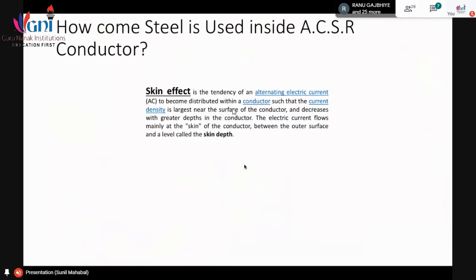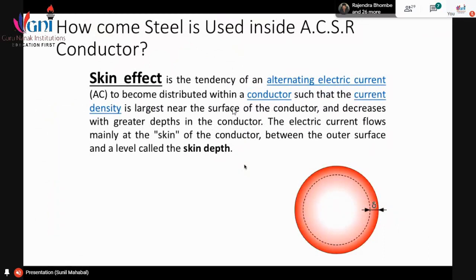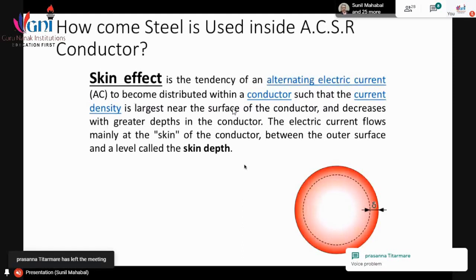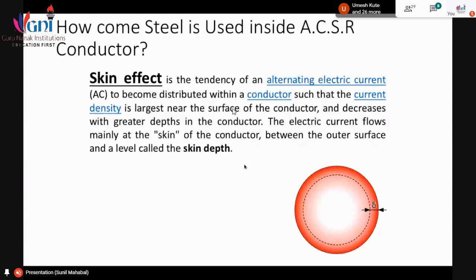Then how come steel is used inside the ACSR conductor? The reason is obvious: it is because of the skin effect. The alternating current has a tendency to distribute in the conductor such that the current density is largest near the surface only. There is no current at the core, and therefore the steel wires, which are not very good conductors as compared to aluminum, can be used inside the aluminum conductor to give mechanical strength to the wire. So the main purpose of steel wires is to give mechanical strength to the aluminum conductor. So it is because of skin effect.